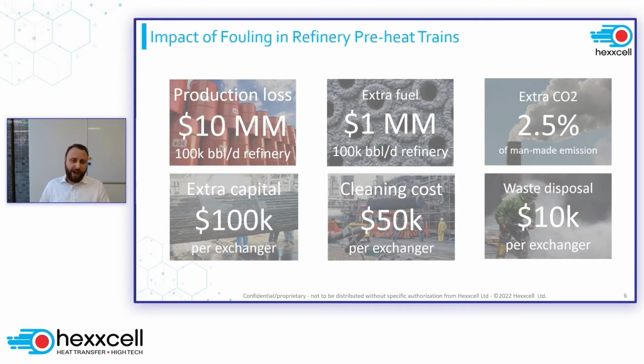The impact of fouling and the losses it generates in the preheat train have been evaluated at very large amounts of money in terms of production losses - about $10 million for a 100K barrel a day refinery - plus significant extra fuel needed at the furnace and significant CO2 emissions. This figure of 2.5% of man-made emissions due to fouling in the preheat train of the crude distillation unit is what you find in the literature. It's perhaps a bit too high these days - we see a little less - but nonetheless it's a very large number.